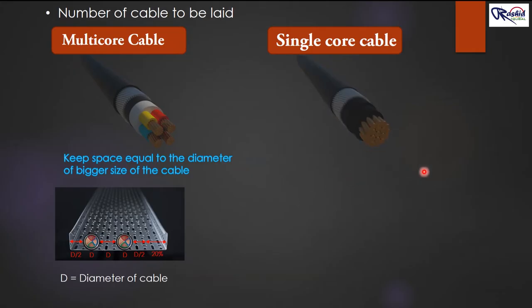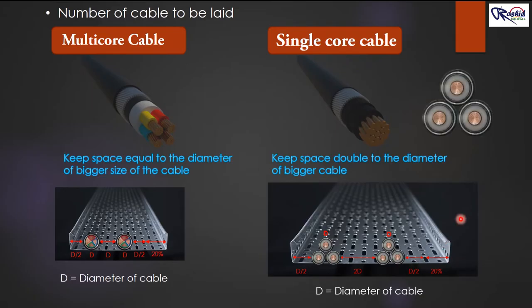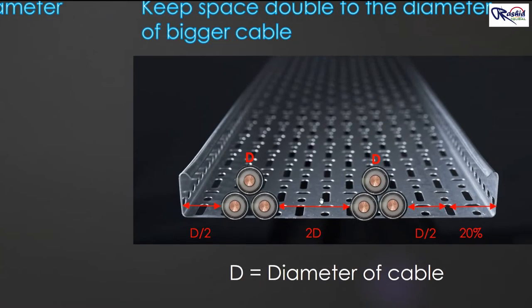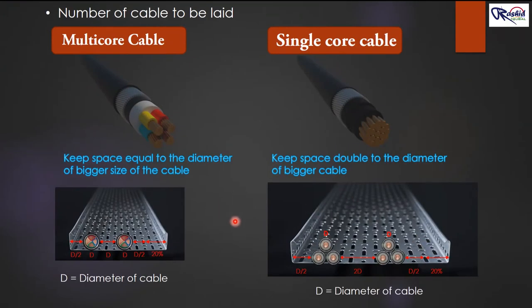For single core cable, we use a trefoil arrangement — trefoil arrangement means three single core cables laid together with different phases: R, Y, and B. If we have to lay two sets of trefoil arrangement in the cable tray, the distance between the two trefoil arrangements is equal to double the diameter of the bigger size cable — that is 2D. The distance between the trefoil and the flange of the cable tray is half the diameter of the cable, that is D/2, on both sides. Then we keep 20 percent extra space for future use.